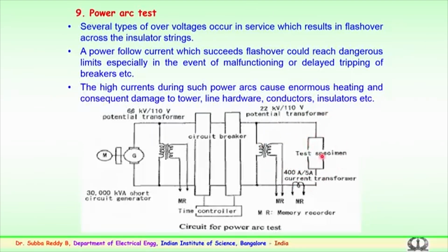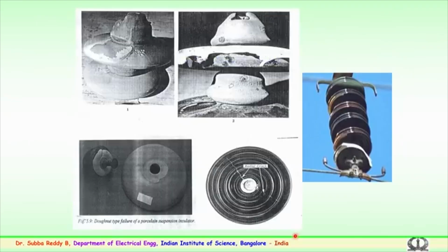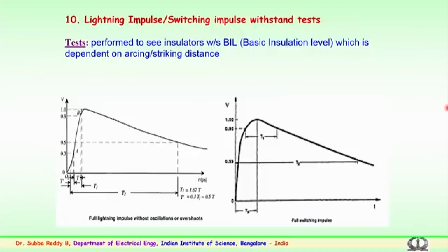In this power arc testing, the samples are impinged with a kVA rating as per the field conditions, and a few cycles of that are applied and the performance is monitored as per the standards. So, these are a few examples of failures which have happened because of various conditions in the field. Similar simulations are necessary to be done in the laboratory conditions.